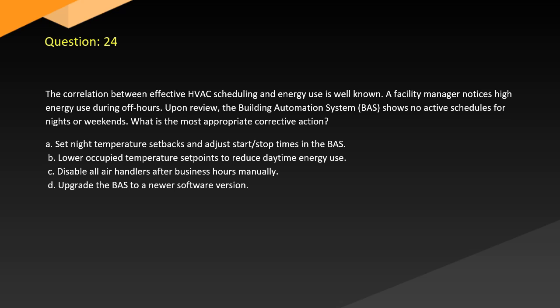Question 24. The correlation between effective HVAC scheduling and energy use is well known. A facility manager notices high energy use during off hours. Upon review, the building automation system (BAS) shows no active schedules for nights or weekends. What is the most appropriate corrective action? A. Set night temperature setbacks and adjust start-stop times in the BAS. B. Lower occupied temperature setpoints to reduce daytime energy use. C. Disable all air handlers after business hours manually. D. Upgrade the BAS to a newer software version.